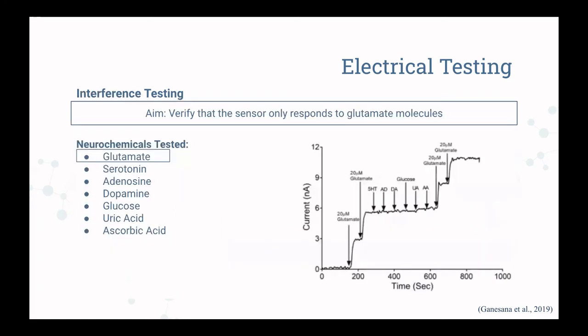Next, we will verify that the device only responds to glutamate and there is no interference by other neurochemicals. To do this, a concentration of the neurochemicals shown on this slide will be injected into the electrochemical cell in vitro over time. We will measure the current produced from the oxidation reaction by the working electrode. As shown in the graph, we expect that the curve will be flat for all the neurochemicals other than the glutamate, where the slope should increase.